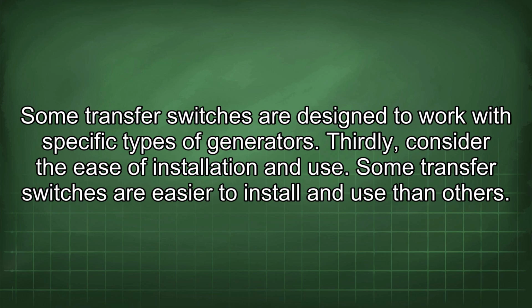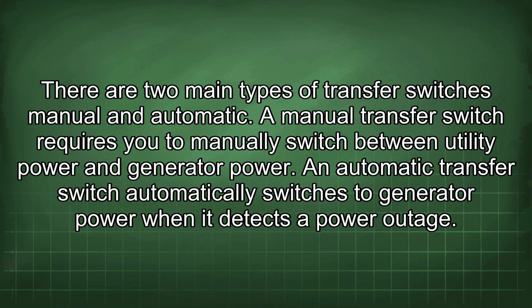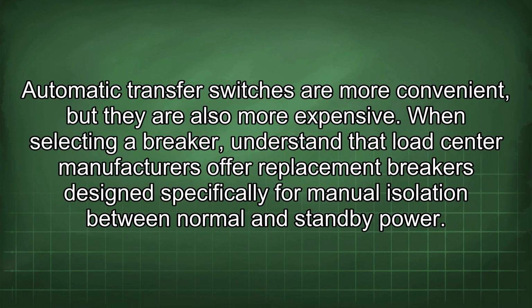Thirdly, consider the ease of installation and use. Some transfer switches are easier to install and use than others. There are two main types of transfer switches: manual and automatic. A manual transfer switch requires you to manually switch between utility power and generator power. An automatic transfer switch automatically switches to generator power when it detects a power outage. Automatic transfer switches are more convenient, but they are also more expensive.